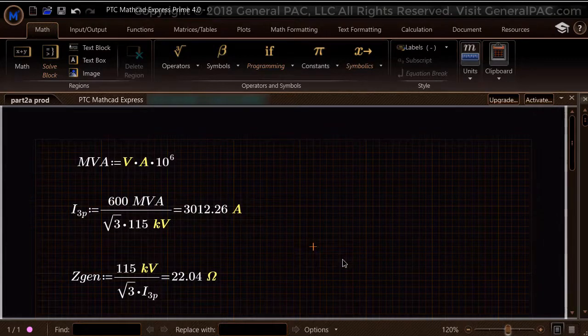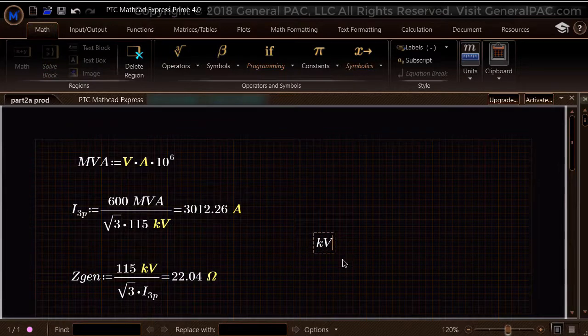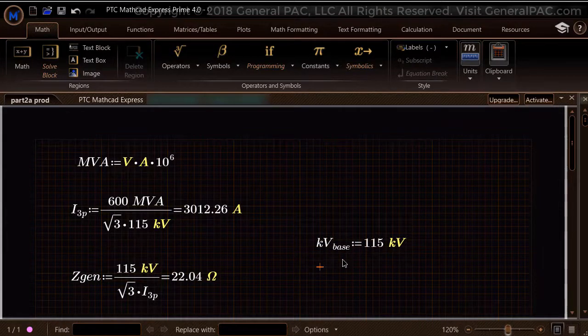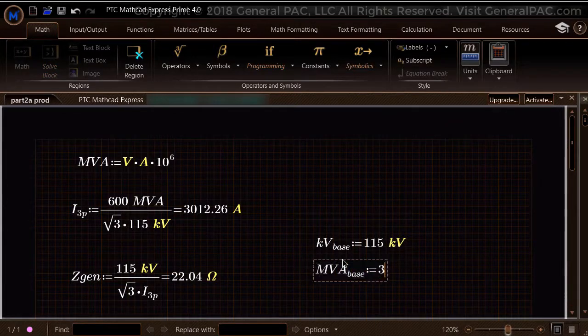Hand calculated short circuit currents are best performed in the per unit system. So let us select the base units. We have already selected the base for the voltage which is 115 kV. Let us strategically select a power base of 30 MVA.